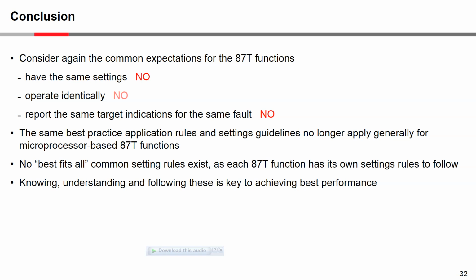So can the protection engineer, can the settings engineer, have the expectation that these 2 relays will have the same settings? No. You would have to look at what the manufacturer is saying, and based on, in particular, how the restraint current is being calculated, there would be those rules defined.